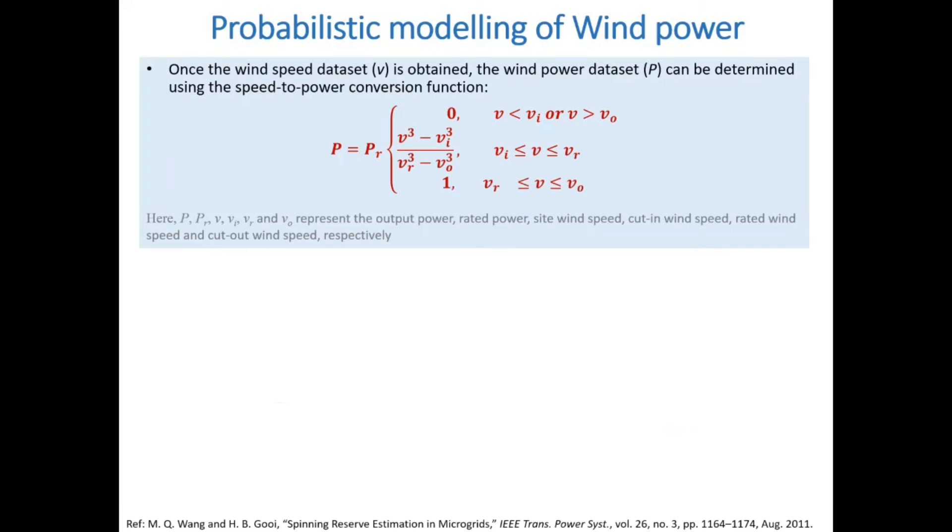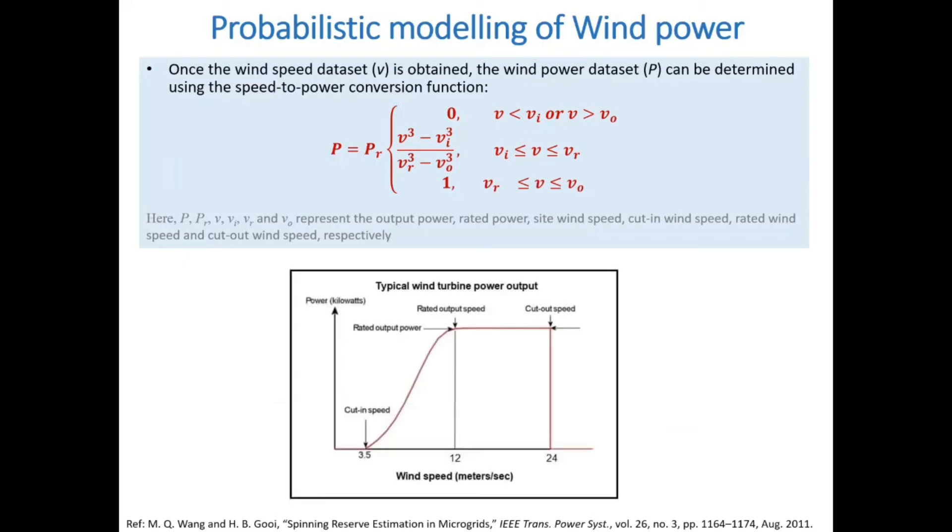Once the wind speed data set is obtained, the wind power data set can be determined using the speed to power conversion function shown here. This function can be understood with the help of this diagram. The lowest speed at which the wind turbine starts producing is the cut-in wind speed. If the wind speed increases, the wind turbine produces more power until it reaches its rated capacity.